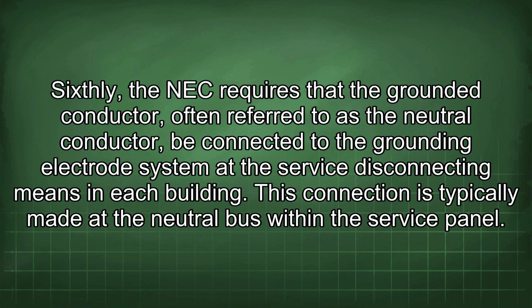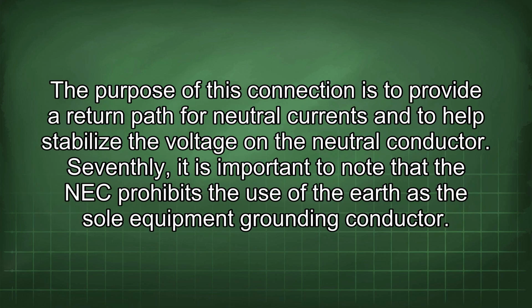Sixthly, the NEC requires that the grounded conductor, often referred to as the neutral conductor, be connected to the grounding electrode system at the service disconnecting means in each building. This connection is typically made at the neutral bus within the service panel. The purpose of this connection is to provide a return path for neutral currents and to help stabilize the voltage on the neutral conductor.